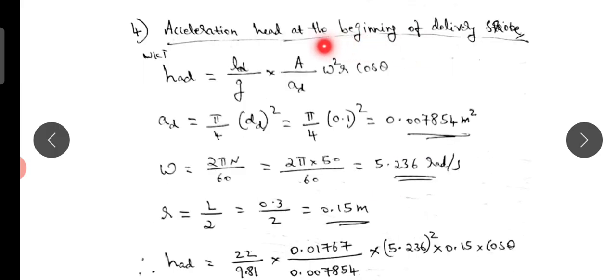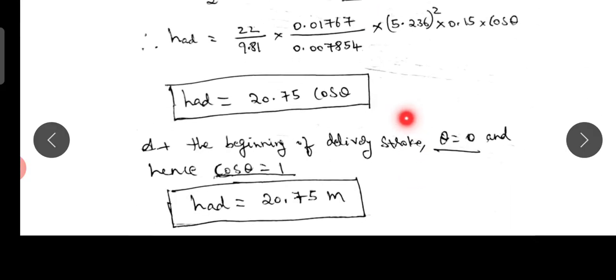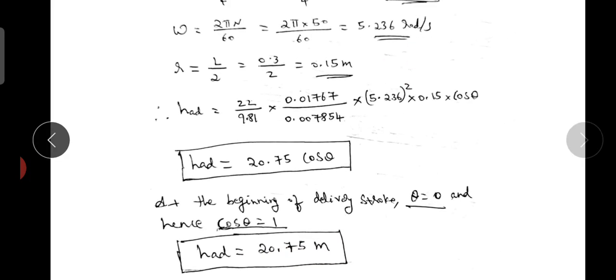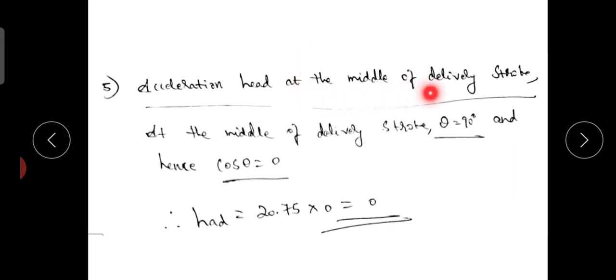At the beginning of the delivery stroke, θ = 0°, so cos θ = 1. At the middle of the delivery stroke, θ = 90°, so cos θ = 0. Substituting all values into the acceleration head formula gives the respective acceleration head values.